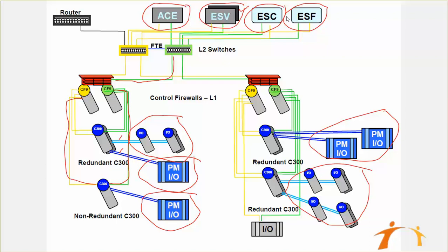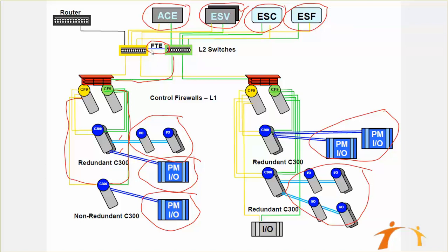All these are connected with your controller via FTE switches, Level 2 switches. You can see that there is a loop in between these two switches, so it provides you not only two paths but four paths to your controller and your different control stations. FTE actually stands for Fault Tolerant Ethernet, so you can tolerate different faults in this.